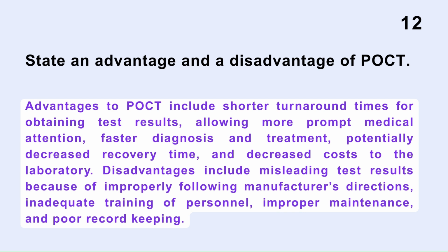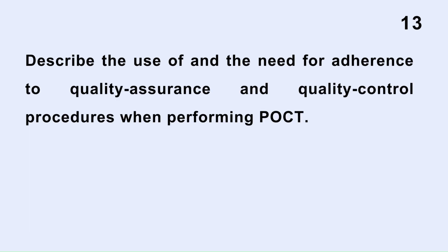Advantages to POCT include shorter turnaround times for obtaining test results, allowing more prompt medical attention, faster diagnosis and treatment, potentially decreased recovery time, and decreased cost to the laboratory. Disadvantages include misleading test results because of improperly following manufacturer's directions, inadequate training of personnel, improper maintenance, and poor record keeping. Describe the use of and the need for adherence to quality assurance and quality control procedures when performing POCT.